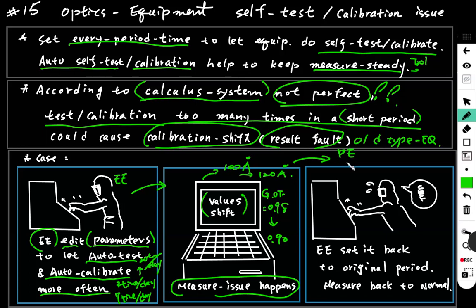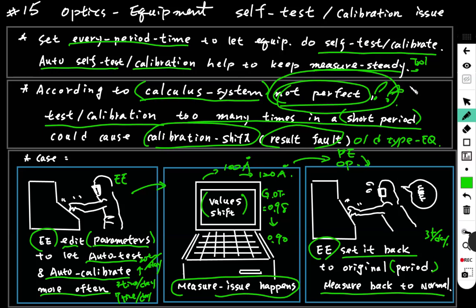the process engineer, the operator, the cost engineer and the equipment engineer got involved. The equipment engineer thought that it was probably the change, so he set it back to the original period, 3 times per day of self-test and self-calibration. The measurement went back to normal. It's very strange. Even if you don't think it's logical, you will find that the calculus system not being perfect is the root cause.